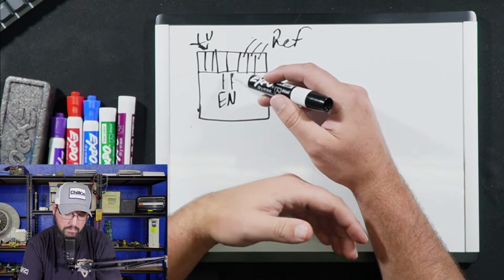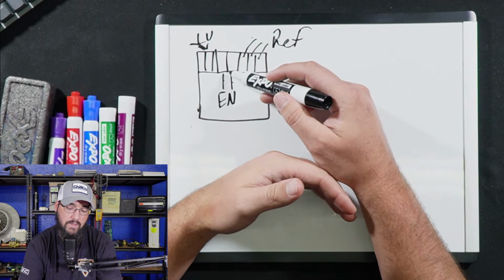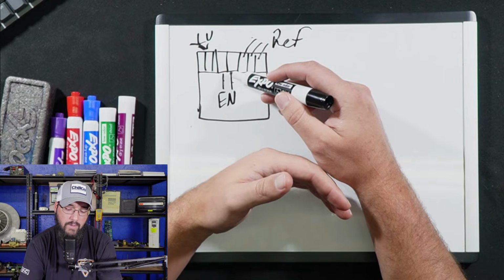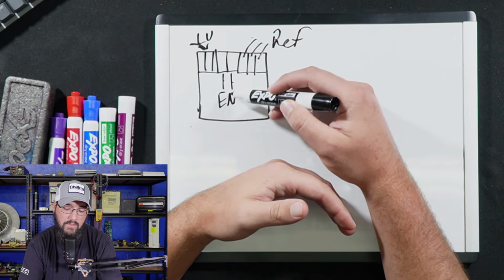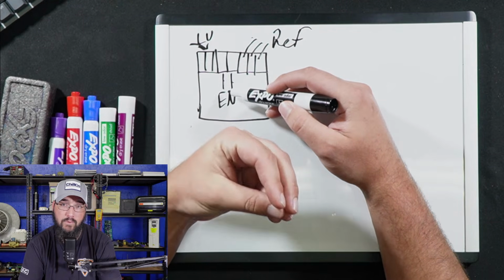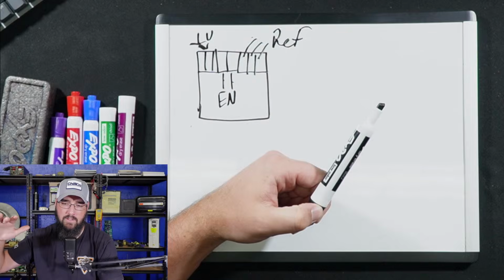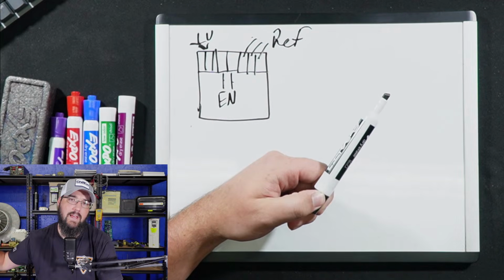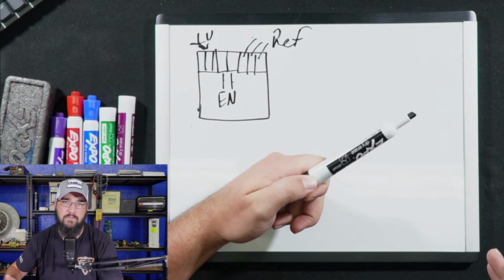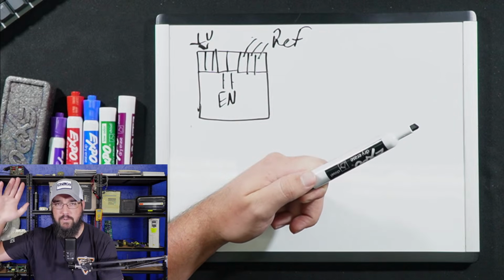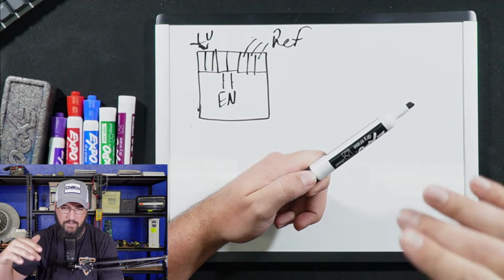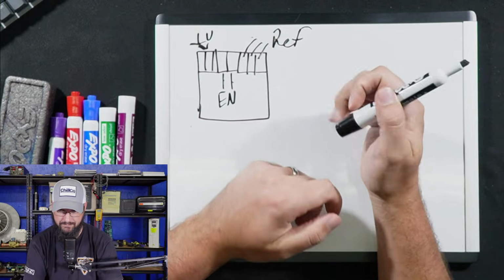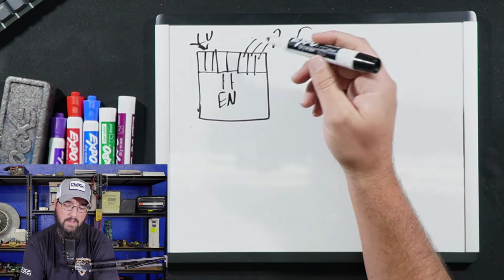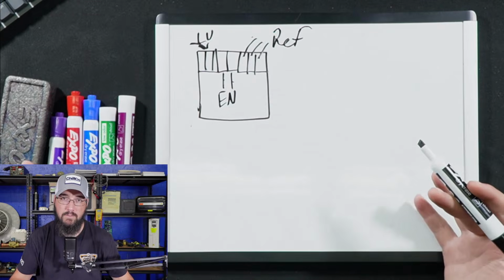So ultimately that was the problem, and the solution was a grounding issue at the fan, causing this enable input to basically freak out, which then faulted the entire fan deck and caused it to shut down mid operation, which then caused pressures to spike suddenly. Everything trips out, we shut down. So yeah, that was the ultimate outcome.